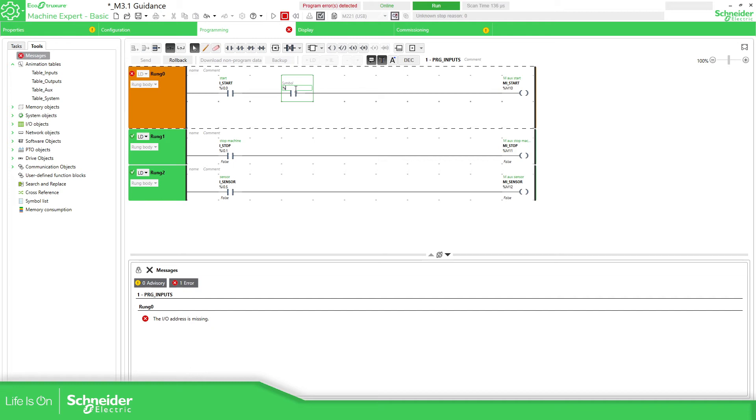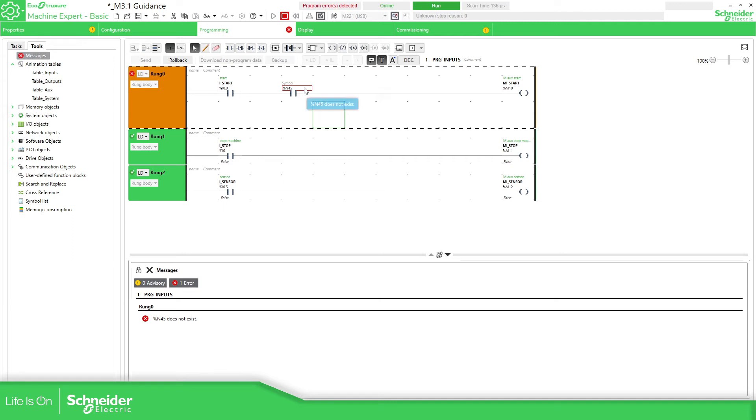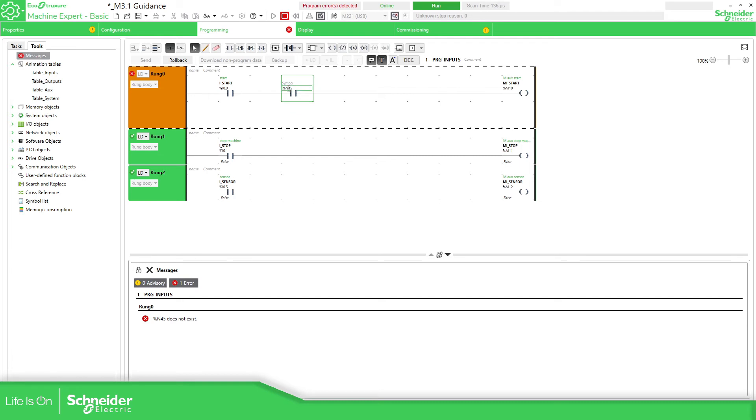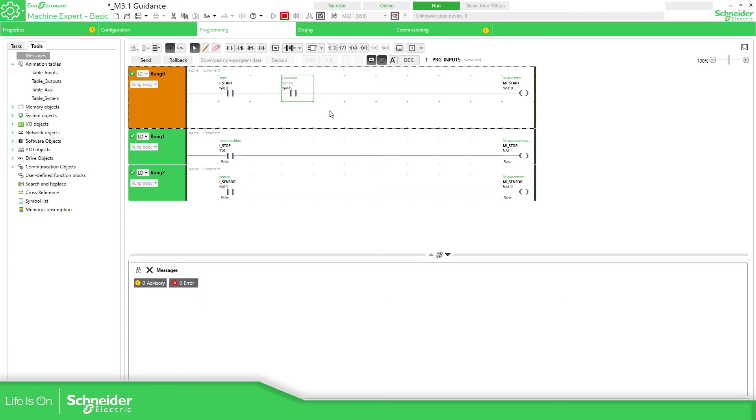Instead of using the M for the memory bits I'm going to use the letter N45. You can see there is something wrong there. The N45 doesn't exist but if I use for example the M45 it allows me. There is no error at all. Even if I don't define this variable we can use it and download to the target.